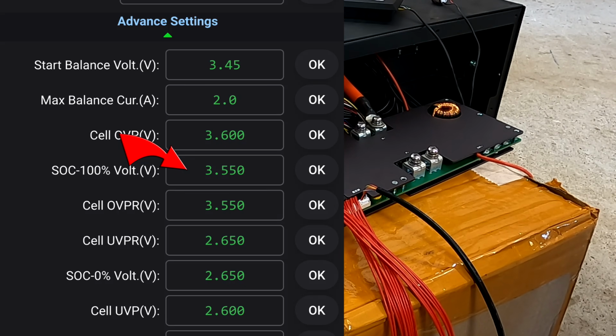Now this is a new parameter in the app, called the state of charge 100% voltage, and it sits at 3.55 volts. At this stage I'm not 100% sure if all the cells need to be over 3.55 volts, or if just one of the cells needs to reach 3.55 volts - we'll find out soon. But this is when the BMS resets to 100% state of charge. There's actually a separate value for this feature in the app, which is highly welcome - this is something we always wanted.